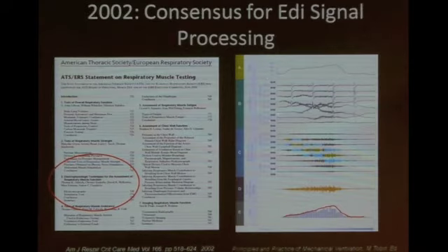This slide shows you the raw EMG signals as they were recorded, and you can see that there's ECG and that there's quite a lot of motion artifact. And then you can see after filtering that we have a more stable signal, and from this we're able to trace the movement of the diaphragm throughout the inspiration using what we call the double subtraction technique. Then we have an accumulated signal, and we calculate the root mean square from this, and then we just connect the dots basically, and we have our EDI waveform.